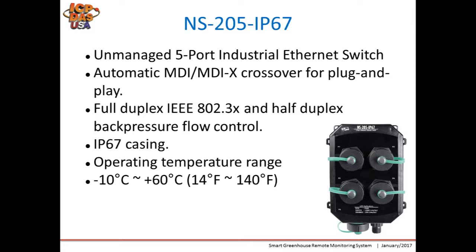Finally, we have IP67 Ethernet switches that can also be deployed in humid and extreme locations so the system has the ability to expand. The NS205 IP67 is an unmanaged five-port industrial Ethernet switch with automatic MDI/MDIX crossover for plug-and-play. It supports full-duplex IEEE 802.3x and half-duplex back-pressure flow control, and can operate from -10 to 60°C. It is fully IP67 rated, meaning it is dustproof and waterproof.